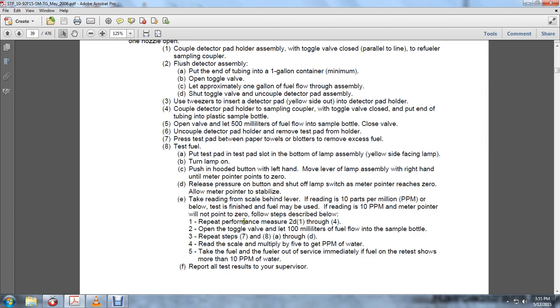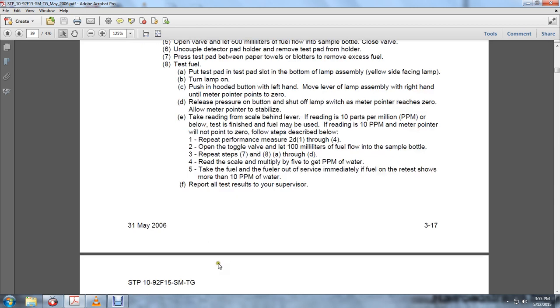Follow the steps described in performance steps 1 through 4. Open the toggle valve and let 100 milliliters of fuel flow into the sample bottle. Repeat steps 7 and 8, A through D. Read the scale and multiply by 5 to get the parts per million of water. Take the fuel filter out of service immediately and retest if the result shows more than 10 parts per million of water. Report all tests and results to your supervisor.